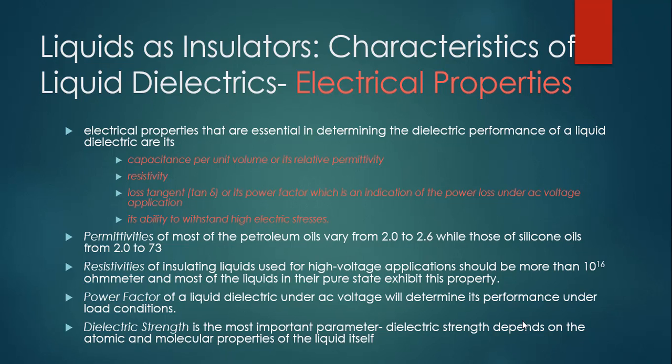Resistivities of the insulating liquids used in high voltage application should be more than 10 to the power 16 ohm meter, and most of the liquids in the pure state exhibit this property.